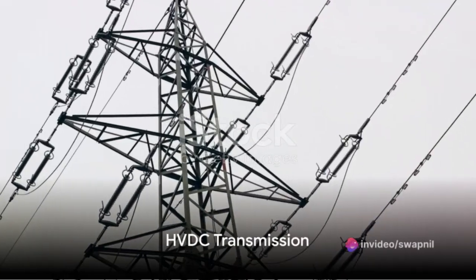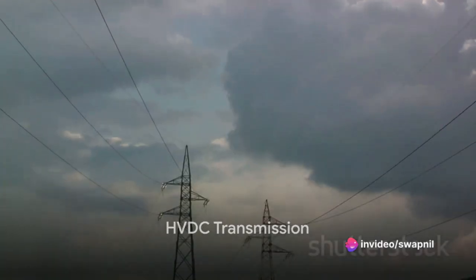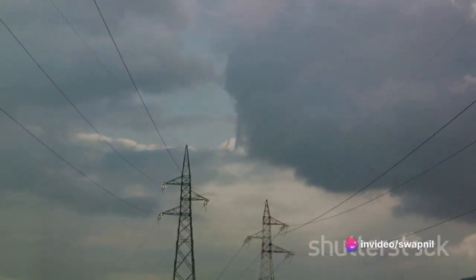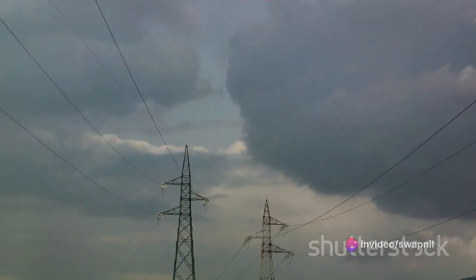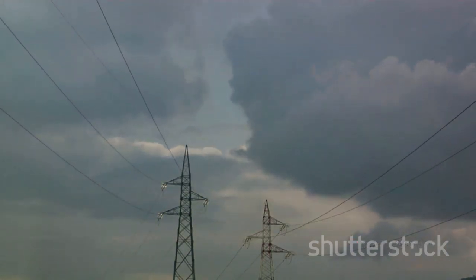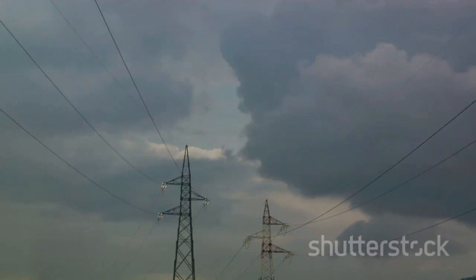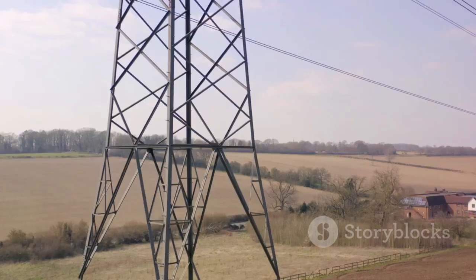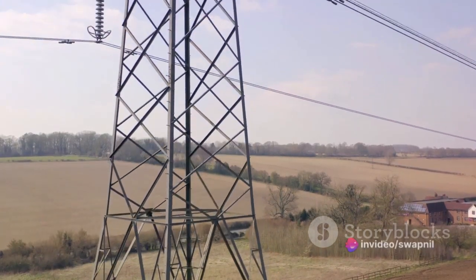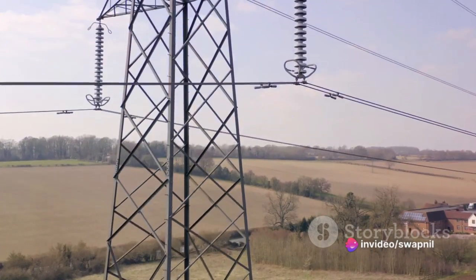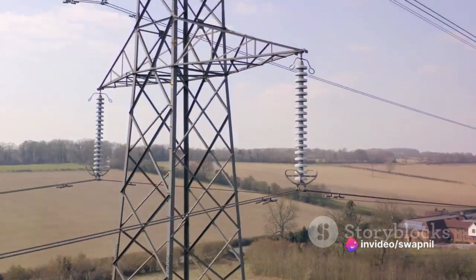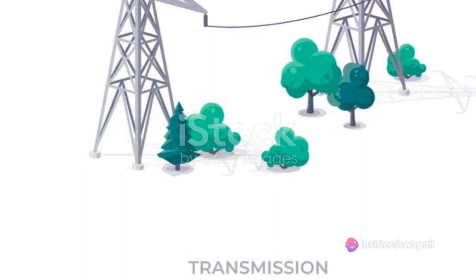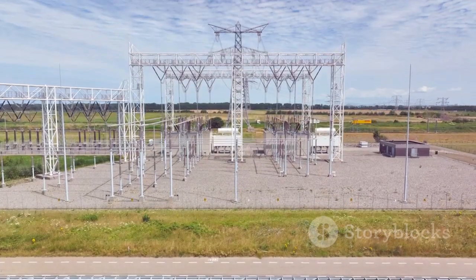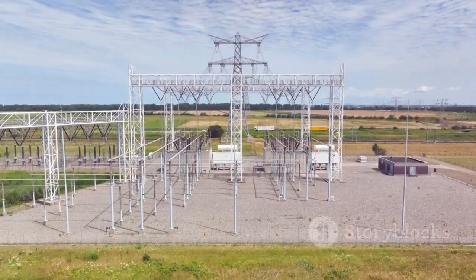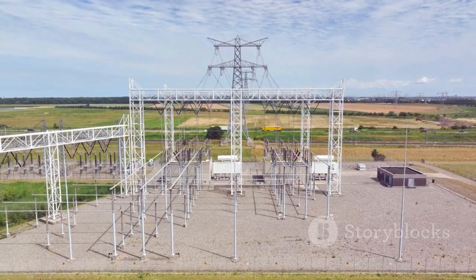The long-distance separation of a generating station from a load center requires long transmission lines of high capacity. The use of AC-DC and DC-AC converters at the terminals of an HVDC line offers a viable alternative. Currently, HVDC transmission has grown up to plus 600 kilovolts with about 4,000 A capacity. The most significant feature of an HVDC transmission network is its full controllability on power transmission.